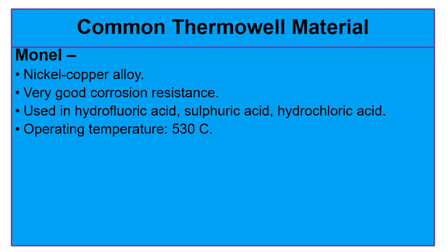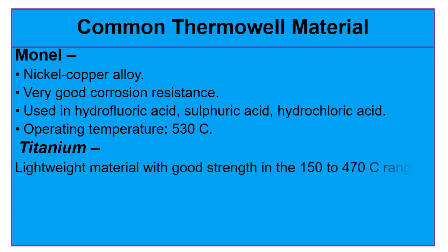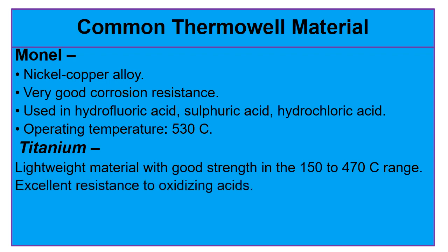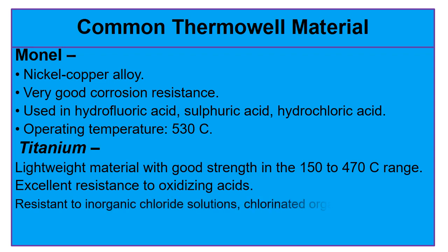The next material is titanium. Titanium is a lightweight material with good strength in the range of 150 to 470 degrees centigrade. It has excellent resistance to oxidizing acids. It is also resistant to inorganic chloride solutions, chlorinated organic compounds, and moist chlorine gases.